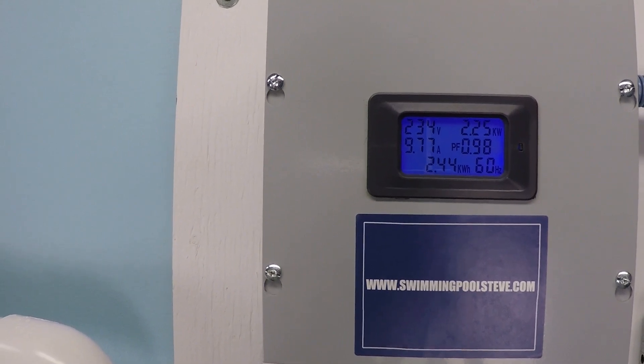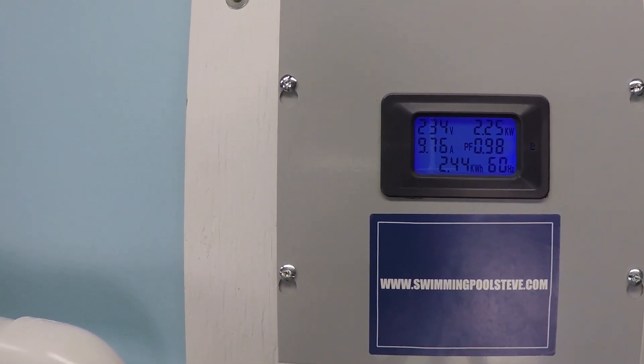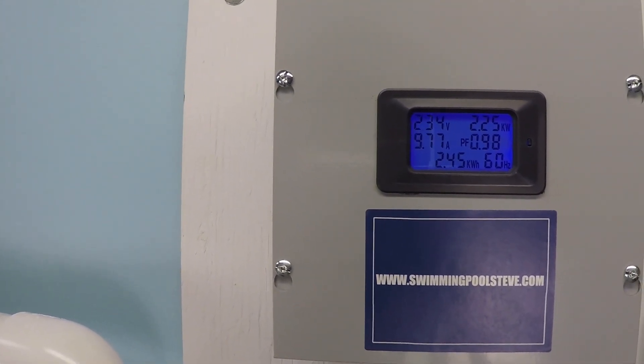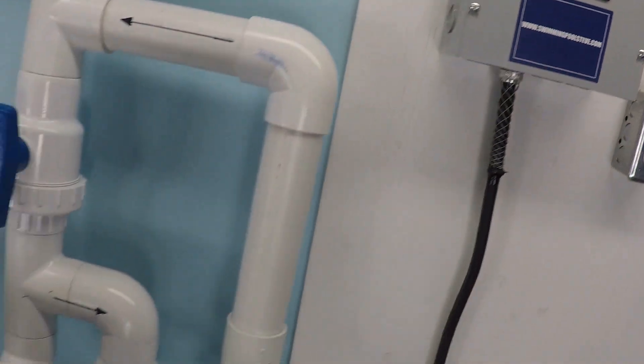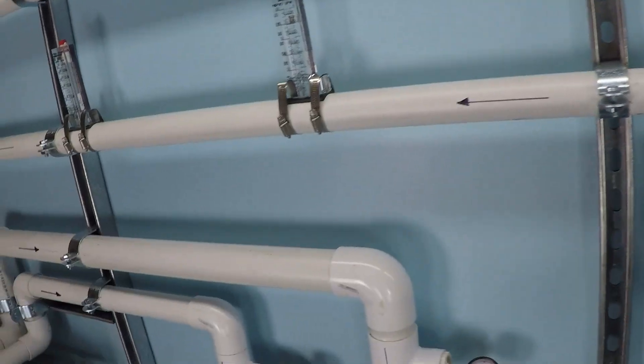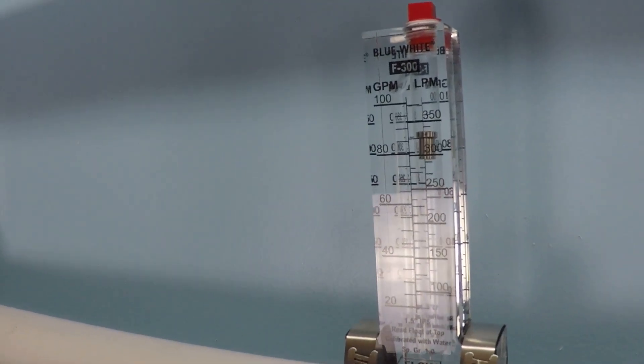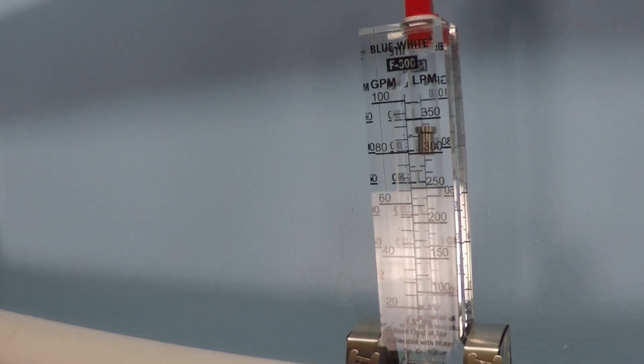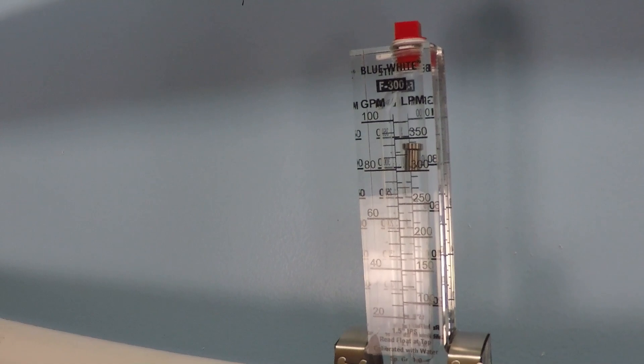9.77 amps, 2.25 kilowatts. Under 90 gallons per minute, I would call that about 88 gallons per minute.